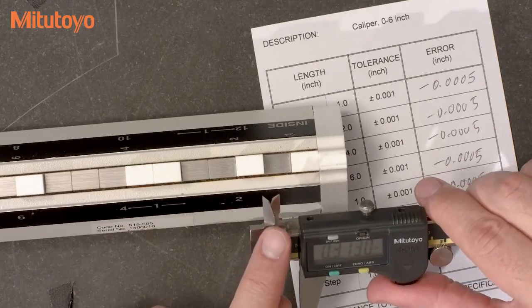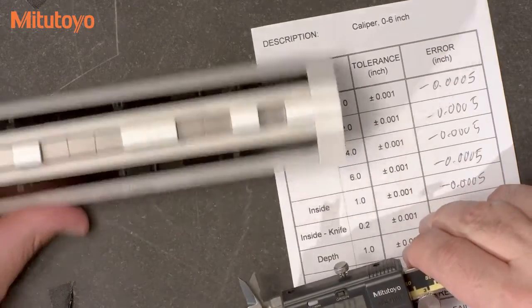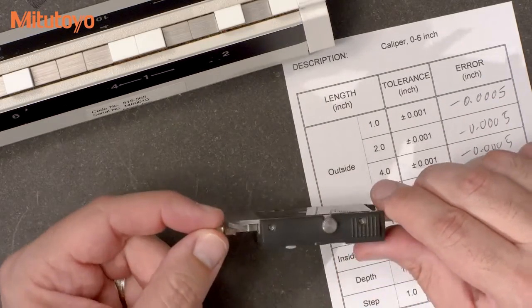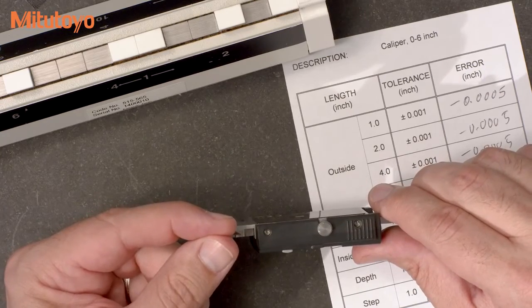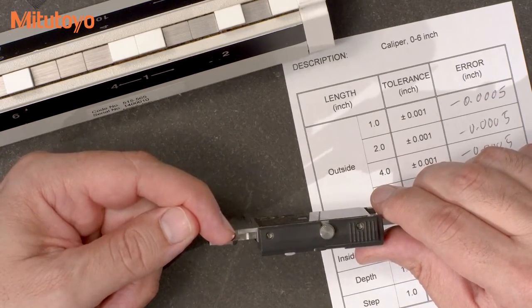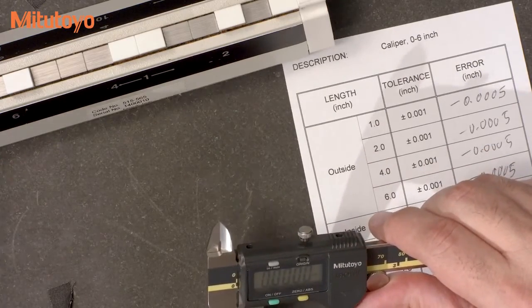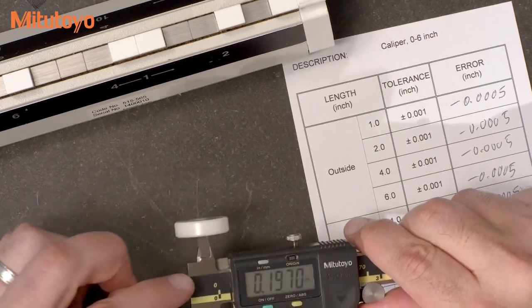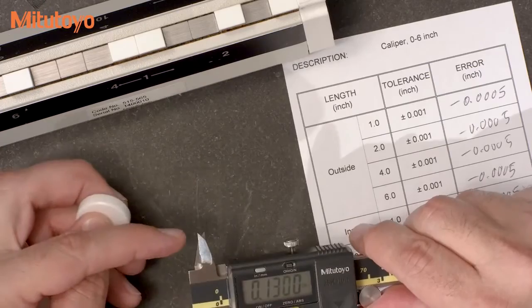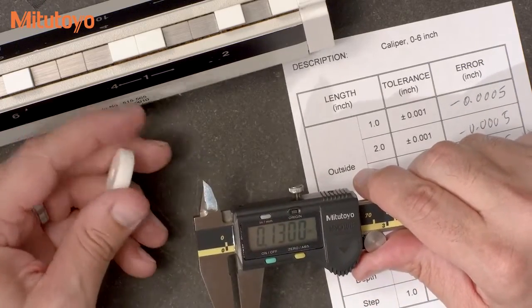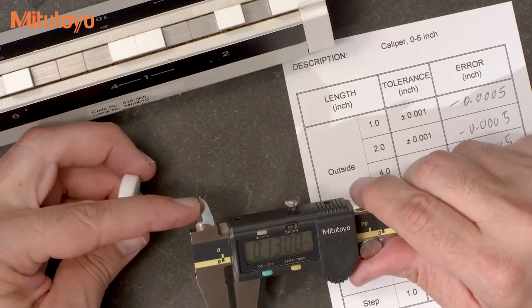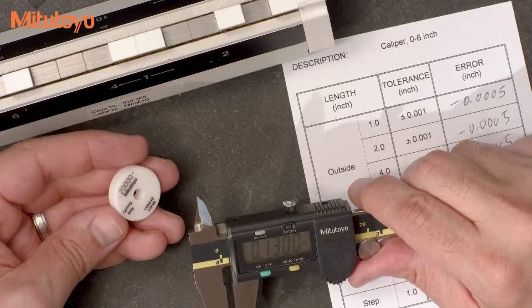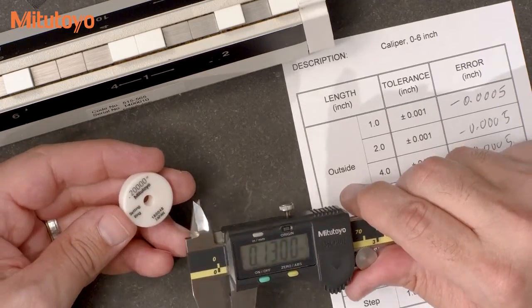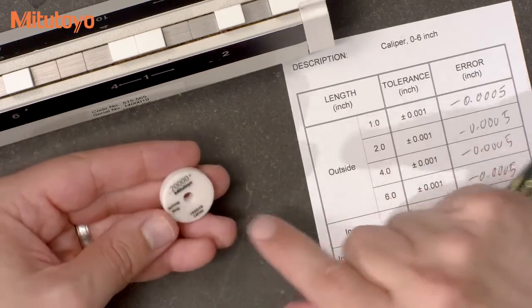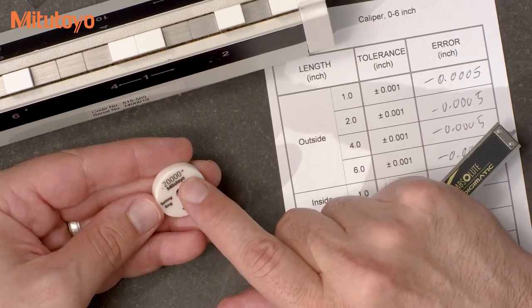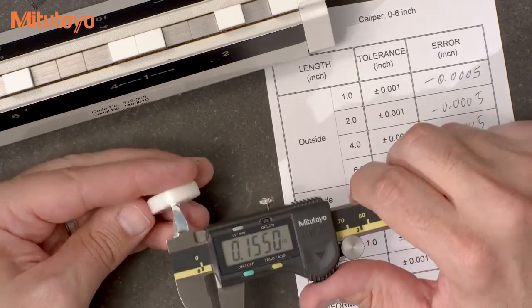This caliper has crossed knife edge inside measuring faces. They are sharp, but of course there is still some thickness to these edge faces, and there's some gap between the two edges. It's pretty well known that if you measure a small inside diameter, you may measure undersize when using the cross knife edge measuring faces. This is particularly a problem when there is some damage to the faces, so it's valuable to check this during calibration. This is done by using a small ring gauge, like this ceramic setting ring. The ASME standard specifies a 0.2 inch diameter for this test, like we have here.